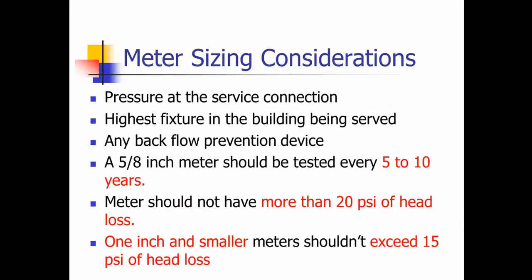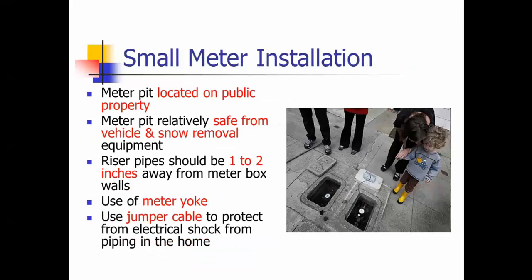On meter sizing, you want to consider the pressure at the service connection. The highest fixture in the building that's going to be served should be a consideration. Any backflow prevention assembly or device is a consideration. A 5/8 inch meter should be tested every 5 to 10 years, and it should not have more than 20 psi head loss across it. 1 inch and smaller meters shouldn't exceed 15 pounds per square inch of head loss across them.